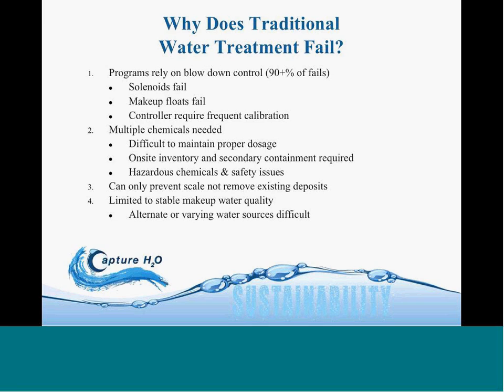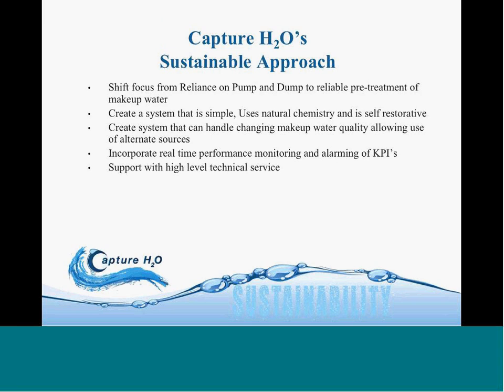And number 4 is these programs typically require very stable makeup water quality. So if you're using alternate water sources like rainwater or groundwater or recycled water or a blend of any, the systems don't function or don't respond well to that changing water quality.